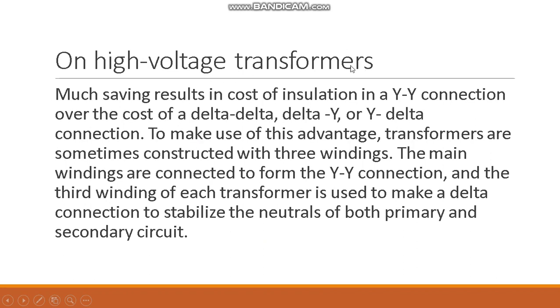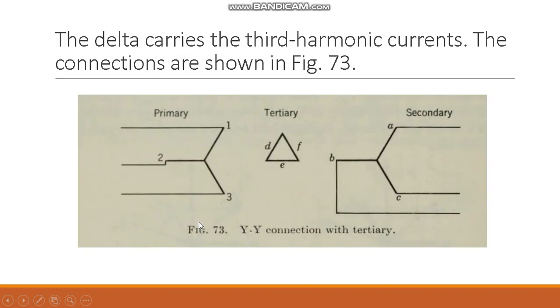At high voltage, much saving results in the cost of insulation in the Y-Y connection over the cost of delta-to-delta, delta-to-Y, or Y-to-delta connection. To make use of this advantage, the transformers are sometimes constructed with three windings. The main windings are connected to form the Y-Y connection, and the third winding of each transformer is used to make a delta connection to stabilize the neutral of both primary and secondary circuits. The delta carries a third harmonic current.